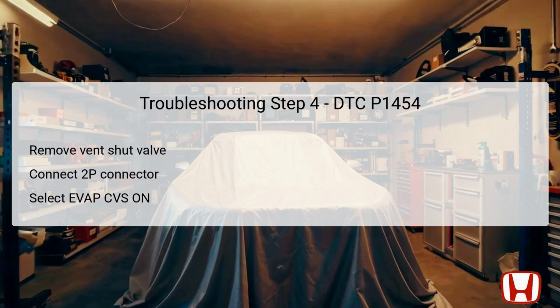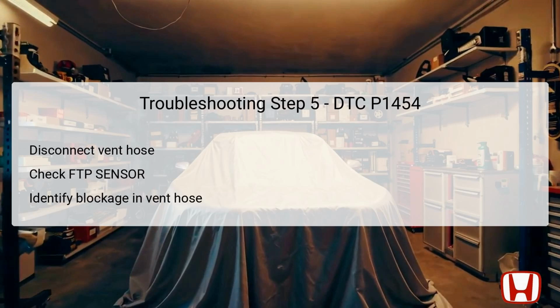Inspect this component for corrosion and functionality. It must operate freely without any obstruction for the system to regulate pressure effectively. If the valve is found to be operational, proceed to the next troubleshooting steps. Now, you'll need to disconnect the vent hose from the FTP sensor. This separation allows for a clear assessment of the sensor's performance independent of the vent line.